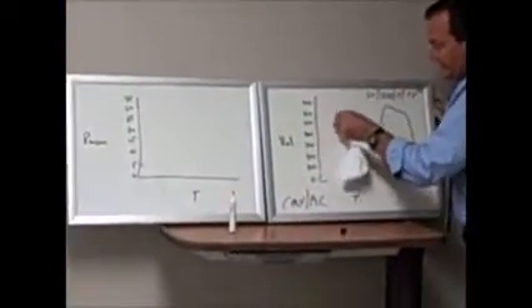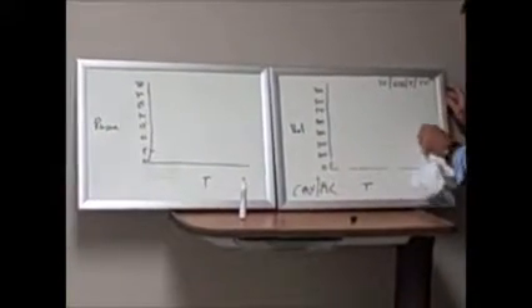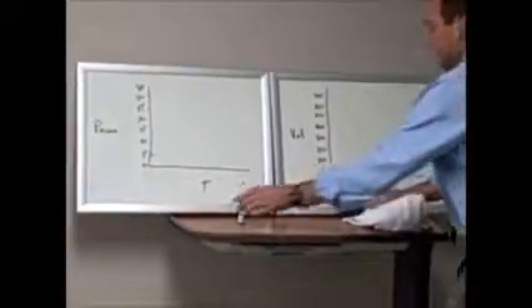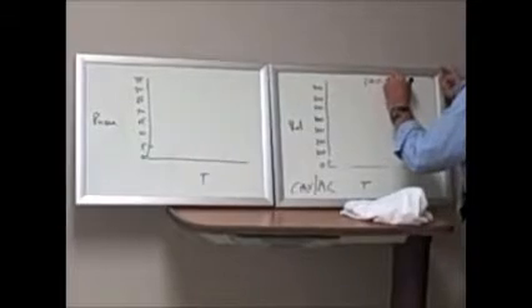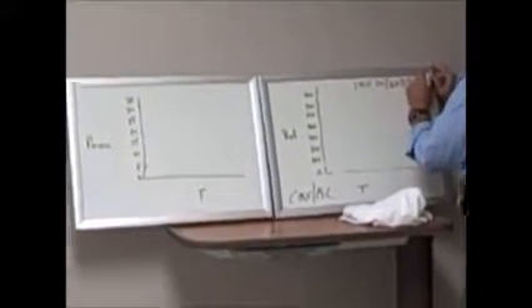So in assist control, the only work of breathing the patient does is to generate enough negative inspiratory pressure to drop the sensitivity and open the demand valve. Fair enough? Fair enough. Let's do IMV with nothing else. Now we got an IMV of 10, tidal volume of 600, PEEP of 5, no pressure support, 50% oxygen. Okay?